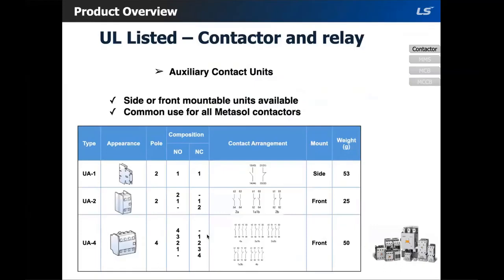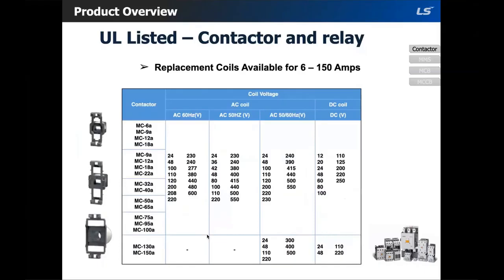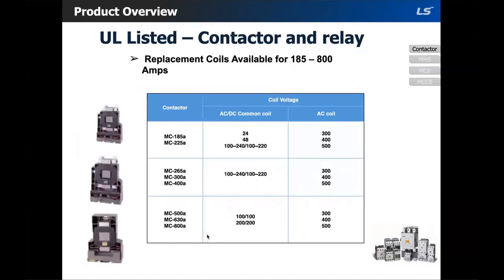And we offer 3 variations of aux contacts: side mount, and 2 front mount variations. These can be used across all the Metasol contactors, so common use for all of them. Replacement coils are also available from 6 amp to 150 amps, and we also have 185 to 800 amps, so it would be dependent. I have a list of stock coils, so if you need coil stock information, I can just send you a list.